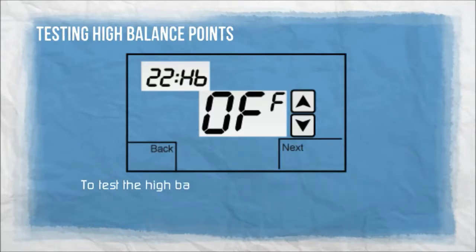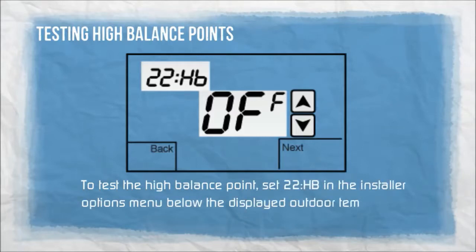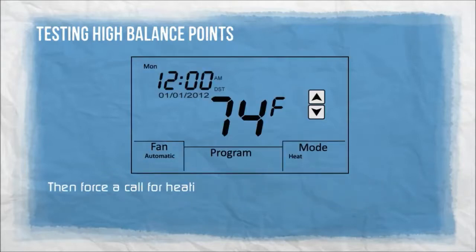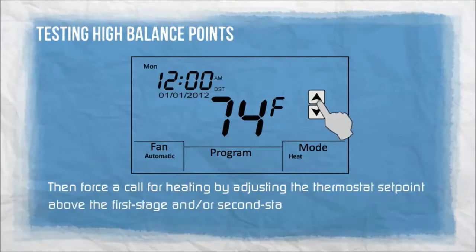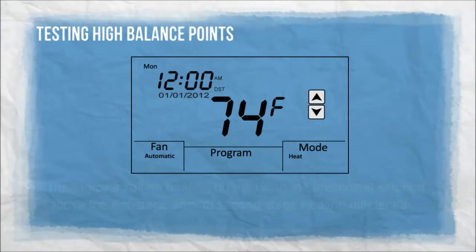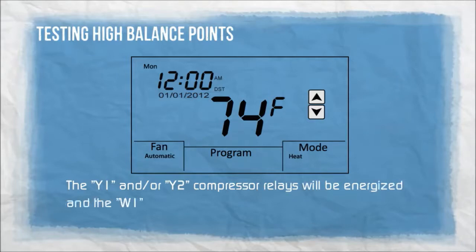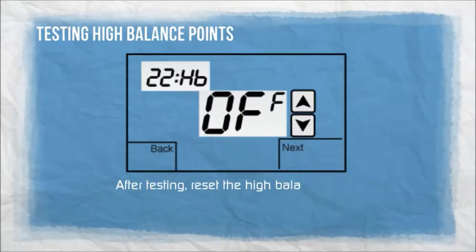To test the high balance point, set 22HB in the installer options menu below the displayed outdoor temperature. Then force a call for heating by adjusting the thermostat set point above the first stage and/or second stage heating differential. The Y1 and/or Y2 compressor relays will be energized and the W1 auxiliary heat relay will be bypassed. After testing, reset the high balance point temperature to a normal operating range.